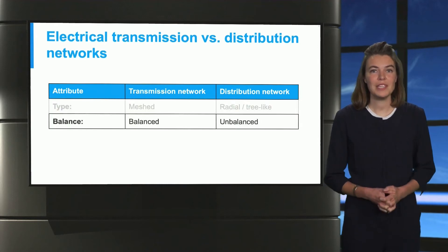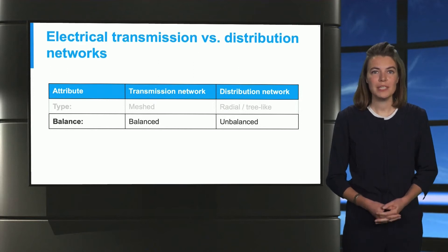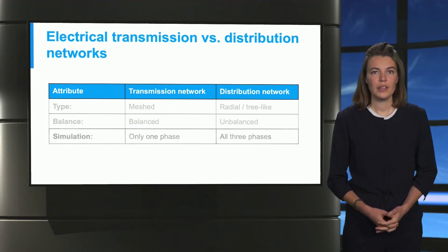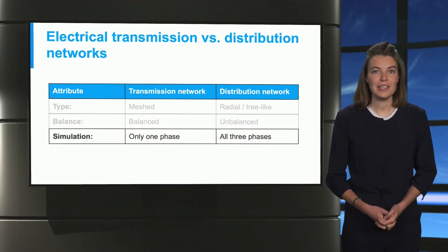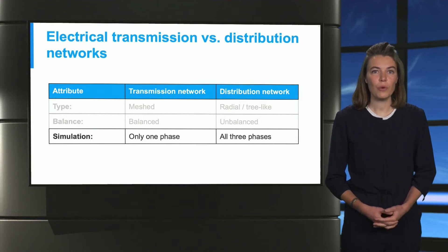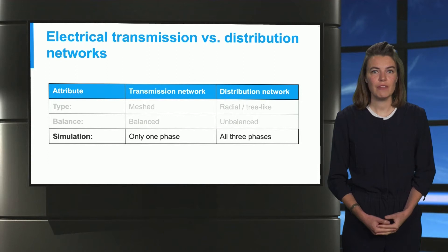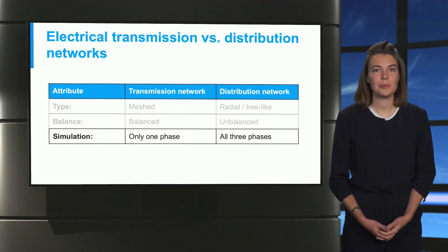Both transmission and distribution networks have three phases, but in the transmission network they are balanced and in the distribution network they are unbalanced. The consequence is that for a transmission network it is sufficient to simulate only one phase, because all phases are in balance and the other phases will simply be a phase shift of the simulated phase. Due to its unbalanced nature, you have to compute all three phases separately in a distribution network.